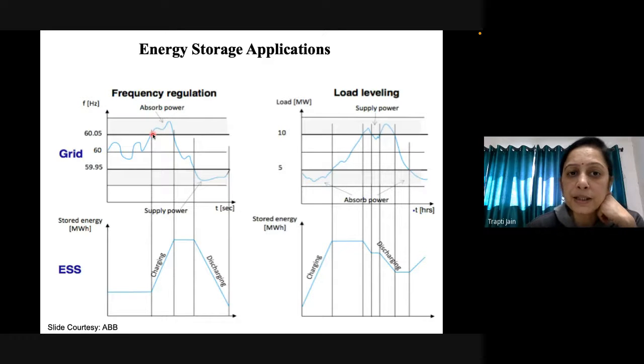But as soon as the frequency goes outside this band and becomes higher, it means generation is high and load is low. So to maintain the balance between generation and load, we need to increase the load by charging these energy storage systems. This charging helps bring down the frequency so it comes back within the band.